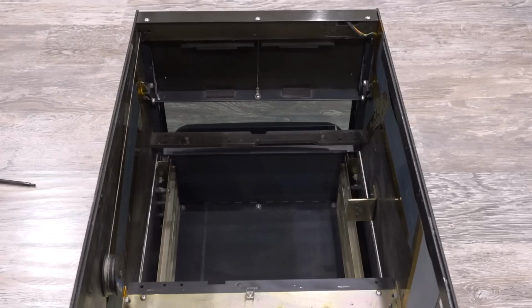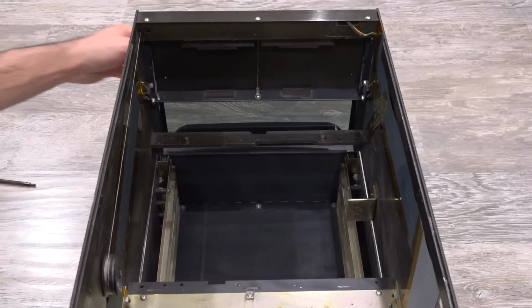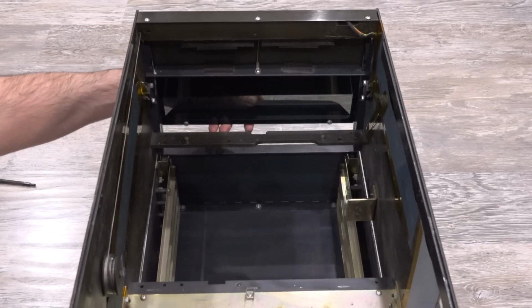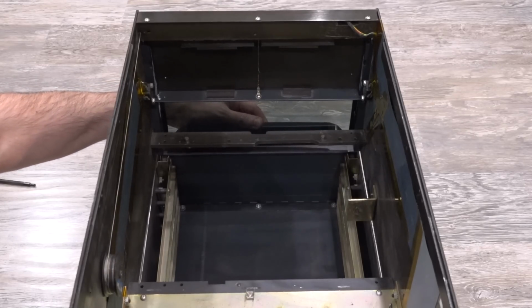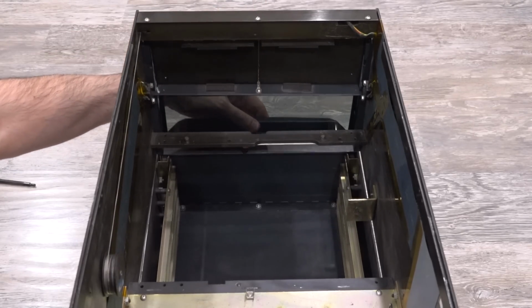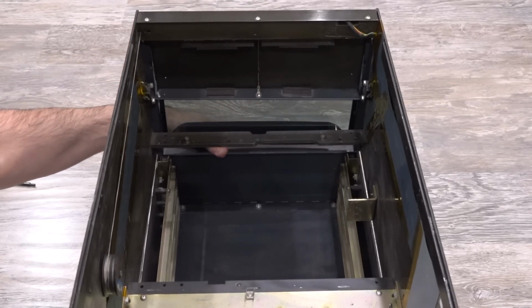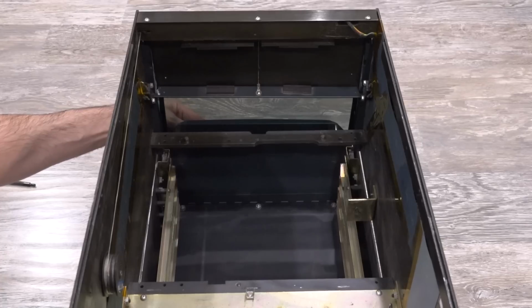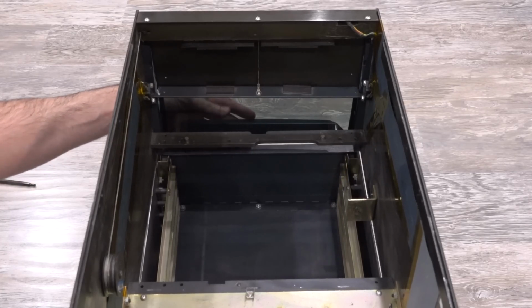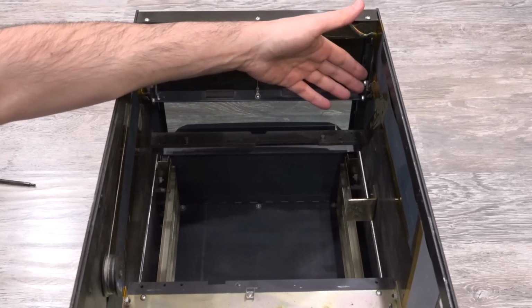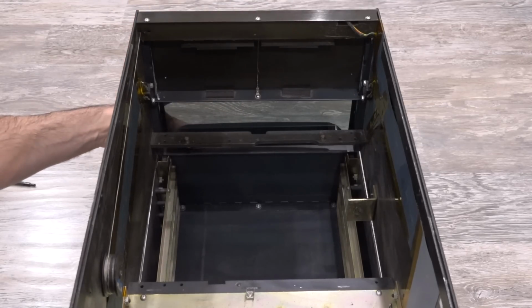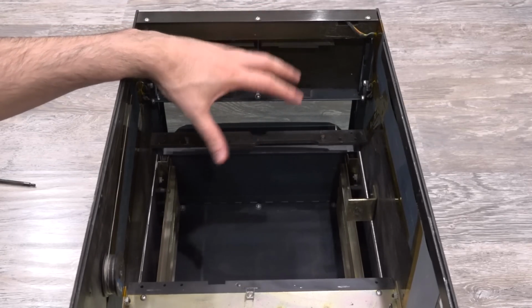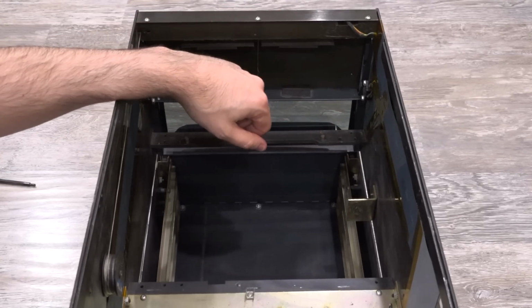So there are two doors in front of the instrument that can be opened. One of them is the glass one. I managed to straighten it out and put it back on the rails. There's a counterweight attached to it via this cable that allows it to kind of smoothly go up and down. And there's a door at the bottom which you can open where you can slide the sample into the unit itself. Interestingly enough, there's two interlocks, one on each side, both for the top door and the bottom door. So there are 4 switches in total that need to be engaged, I'm guessing, for the X-ray to be enabled.